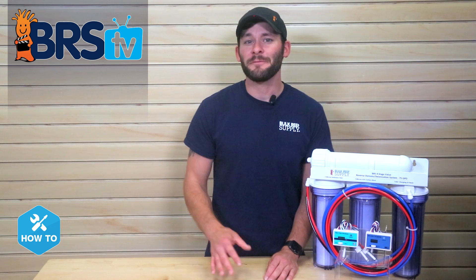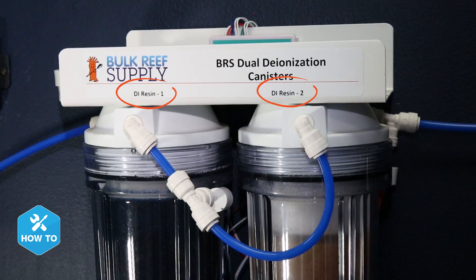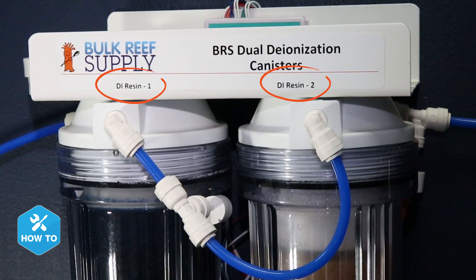Finally, if you have additional sensors to install, you could put one on the line between your tap water and the filter unit. The only thing here is that the TDS concentration in your tap water may not change significantly, so it may be more beneficial to install a sensor after each DI resin cartridge, which will allow you to monitor TDS removal throughout each stage.